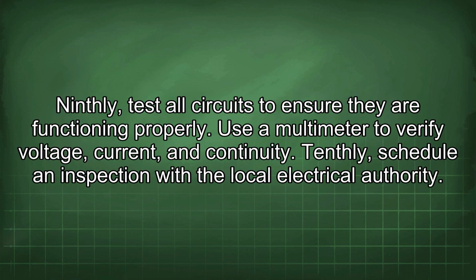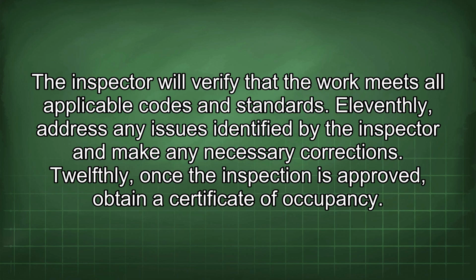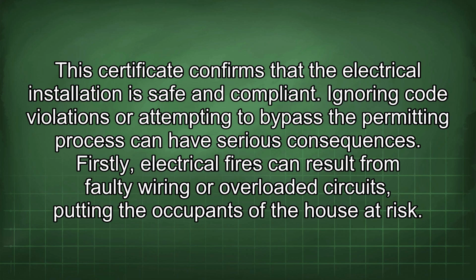Ninthly, test all circuits to ensure they are functioning properly. Use a multimeter to verify voltage, current, and continuity. Tenthly, schedule an inspection with the local electrical authority. The inspector will verify that the work meets all applicable codes and standards. Eleventhly, address any issues identified by the inspector and make any necessary corrections. Twelfthly, once the inspection is approved, obtain a certificate of occupancy. This certificate confirms that the electrical installation is safe and compliant.